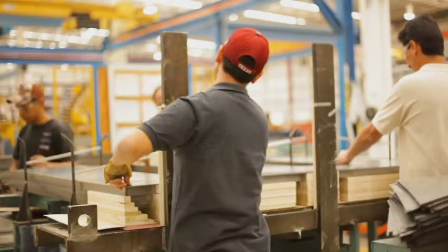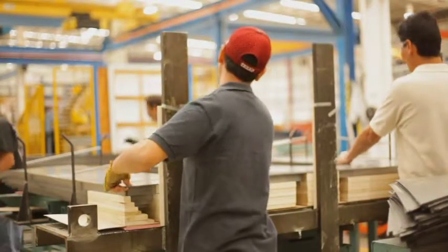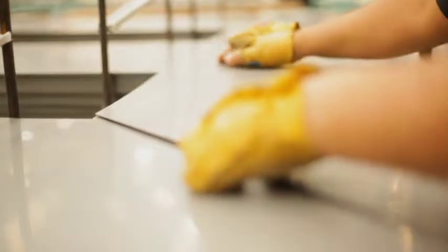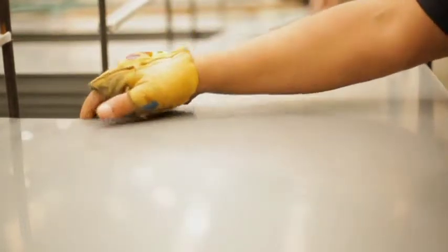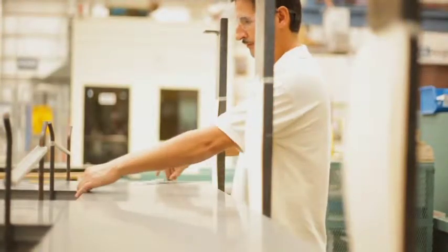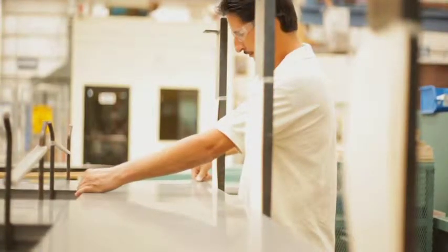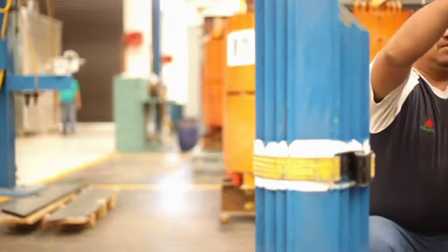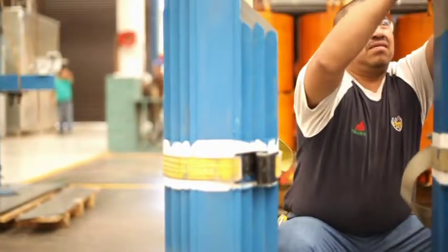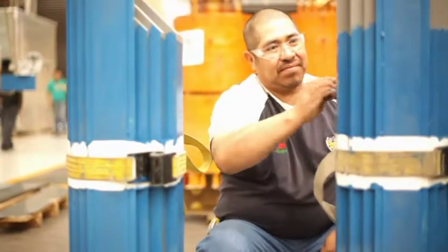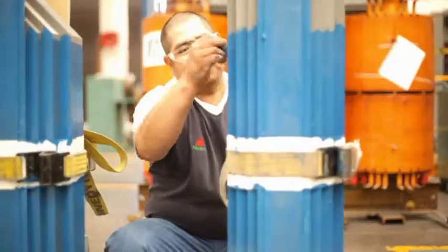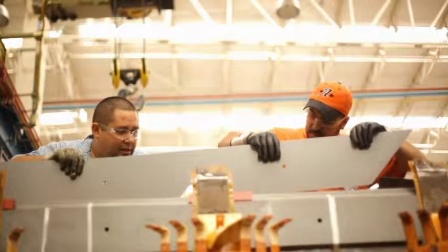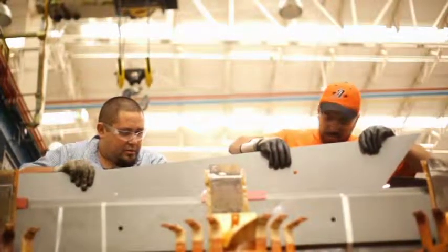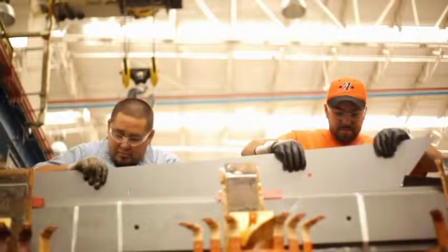Then, these sheets are taken to the core stack area, where steel plates are overlapped with splices based on the type of cut, in order to generate the lowest excitation current possible, as well as to ensure the lowest core losses. The assembly area of core and coil is carefully done, mounting the coils on each leg of the core to ensure optimal support and restraint. Here, the placement of insulators on hardware and top core is also done.